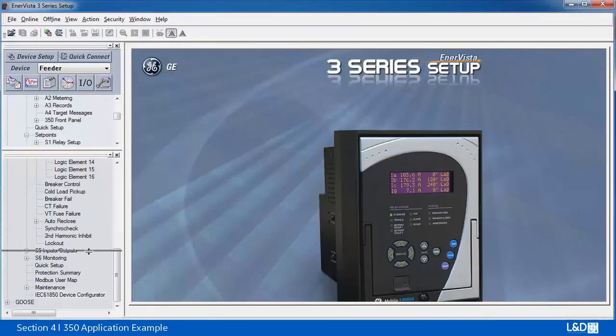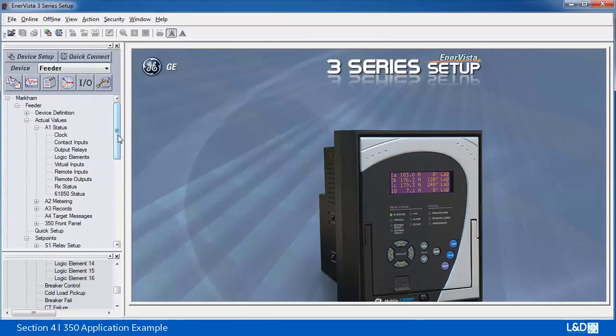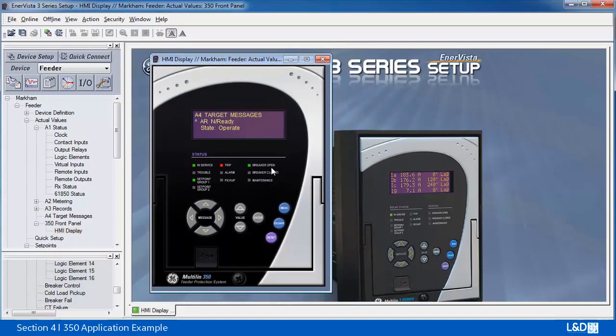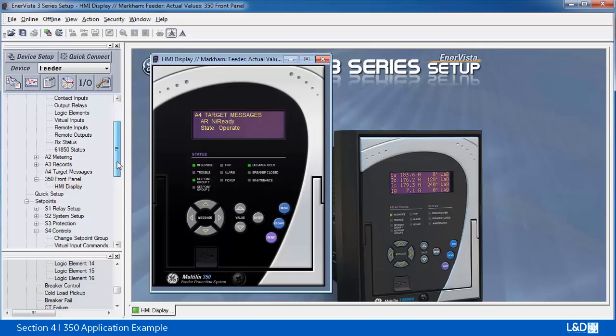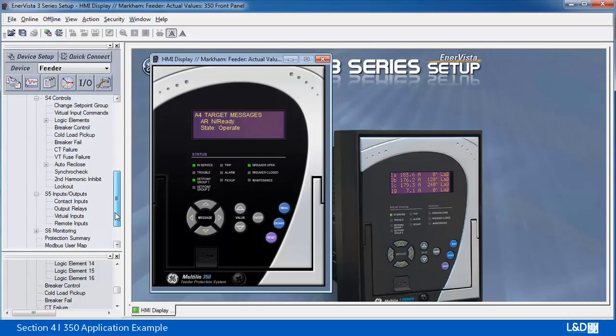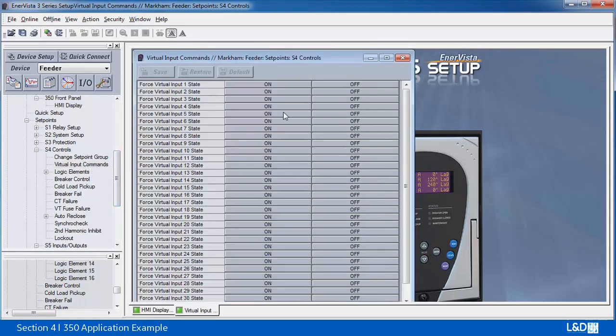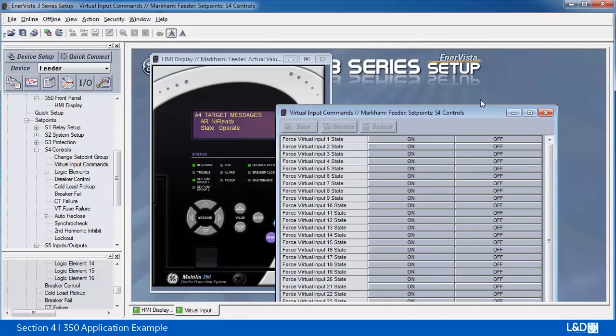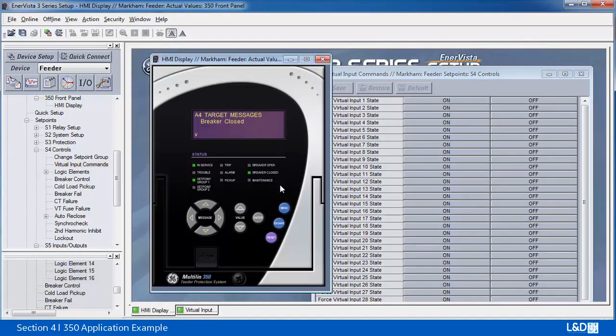So to make this work, this setting will be uploaded into the relay and both relays rebooted. Once this is done, we can start the front panel of the 350 and do the manual close of the breaker by using virtual input 1. Okay, so now we see the breaker status is open. We can reset the front panel trip LED. We're going to close the breaker by using the command. Okay, so once virtual input 1 is closed, we can see that the breaker status is closed. Now the auto reclose is ready.